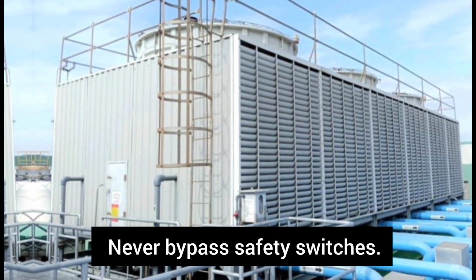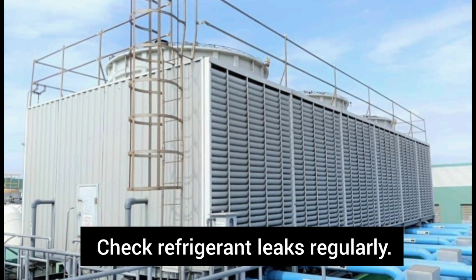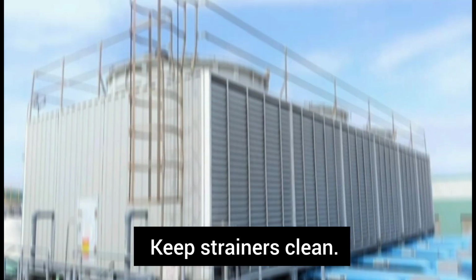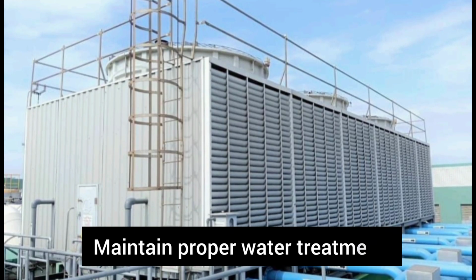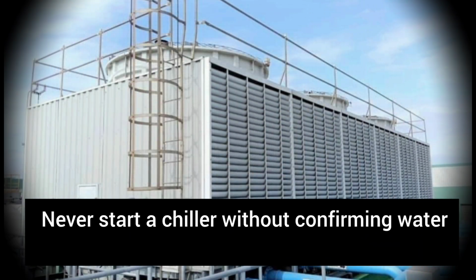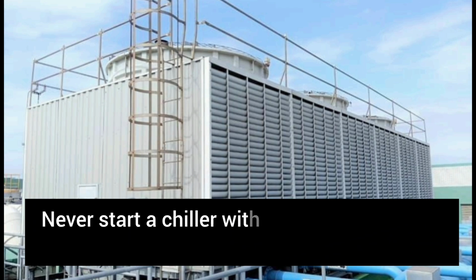Safety tips. Wear PPE. Never bypass safety switches. Check refrigerant leaks regularly. Keep strainers clean. Maintain proper water treatment. Follow the manufacturer's operating manual. Never start a chiller without confirming water circulation.